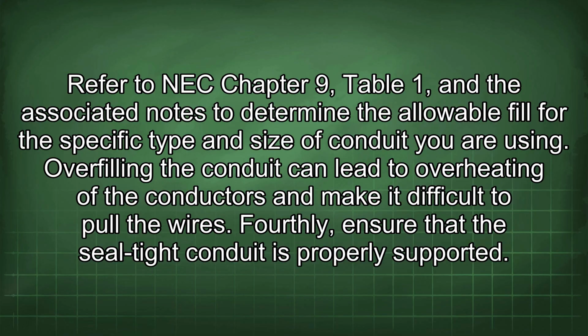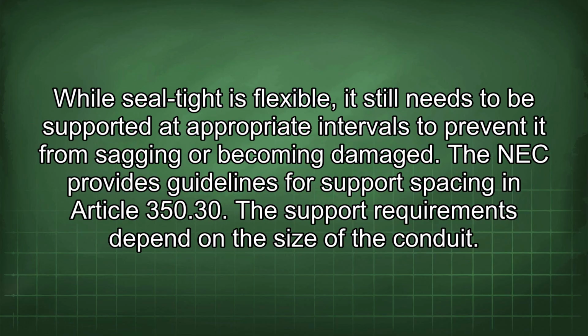Fourthly, ensure that the seal-tight conduit is properly supported. While seal-tight is flexible, it still needs to be supported at appropriate intervals to prevent it from sagging or becoming damaged. The NEC provides guidelines for support spacing in Article 350.30. The support requirements depend on the size of the conduit.